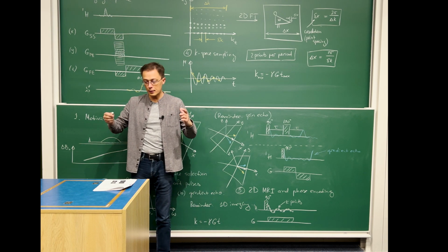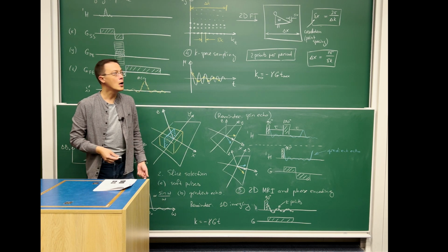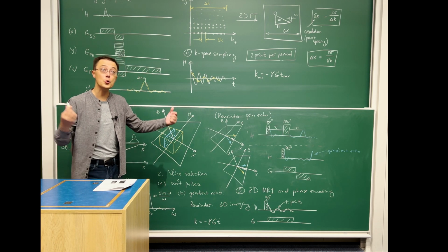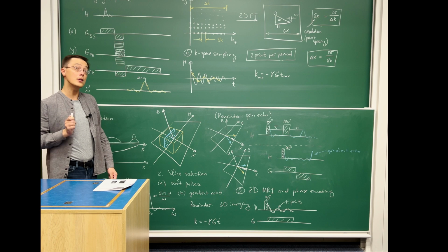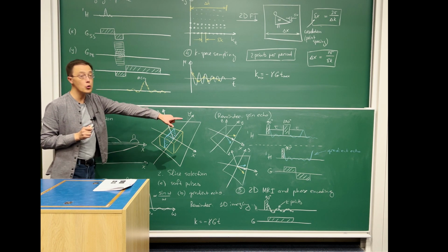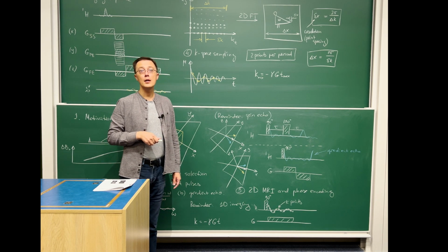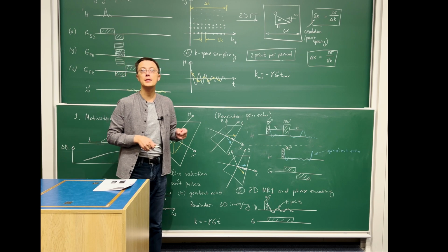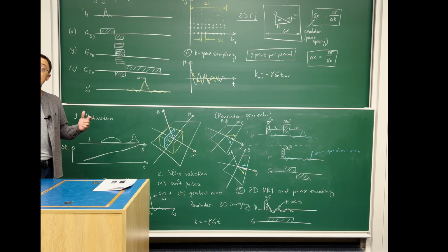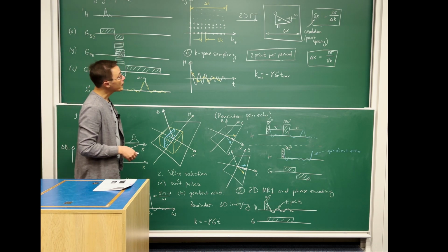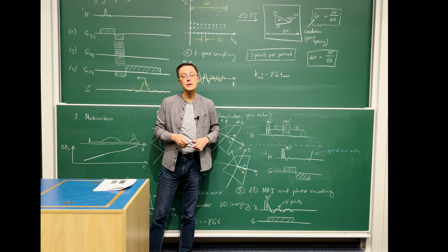Means we have either to have more loops in the gradient coil to increase the induction, or we need to have a greater current through that coil. Both mean a lot of engineering, high precision engineering, because these gradients have to be extraordinarily precise. Remember, 3 Tesla, right, is over 100 megahertz. So you are talking time scales of microseconds to nanoseconds on the precision and the fractional accuracy of all of the electrics that goes on into that instrument. So the stronger the gradients, the higher the resolution the instrument is going to have.